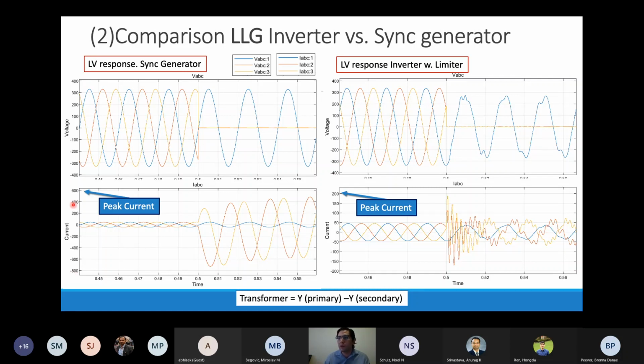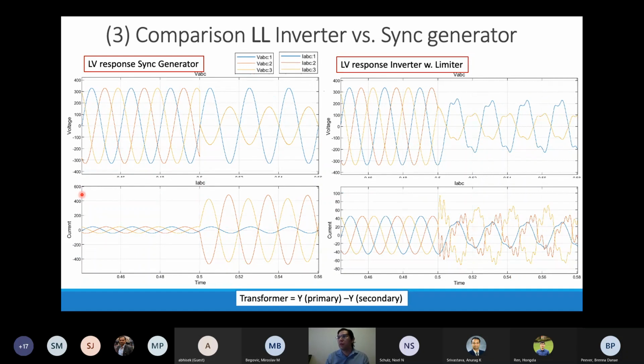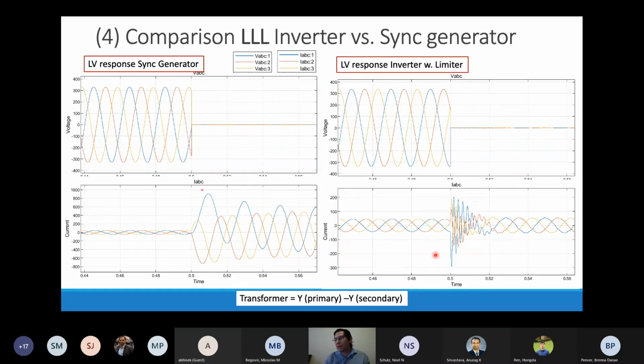It's also good to mention that our figures might look a little alike, but we can see that the magnitudes are totally different. That's the reason why we need a different type of detection when we have faults in inverter-connected systems. Here I'm testing a line-to-line-to-ground fault, again at 0.5 seconds, and the peak current magnitude, as you can see, is way smaller comparing the inverter versus the synchronous generator. Now here I'm testing the triple phase fault, again at 0.5 seconds.